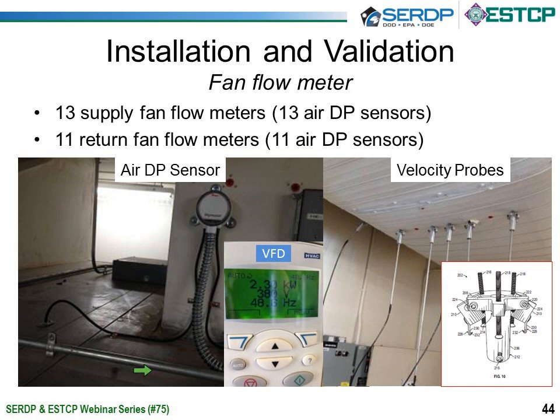On the left, we have a picture of the air DP sensor. In the middle, we have the picture of the VFD display. The VFD data are taken in or communicated to the virtual meter. And I do want to point out on the right that this is the supply duct, or the bottom of the supply duct of the air handling unit.